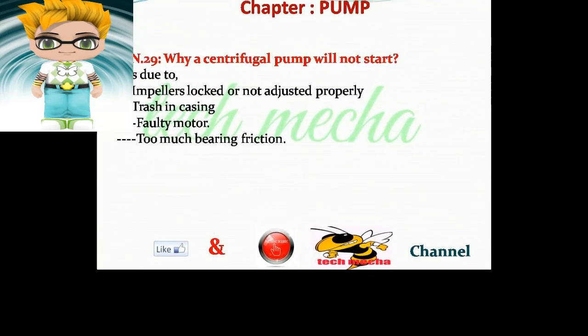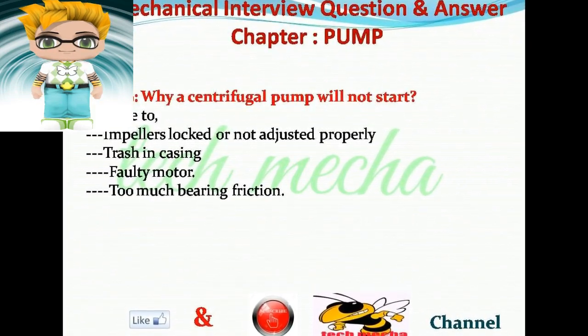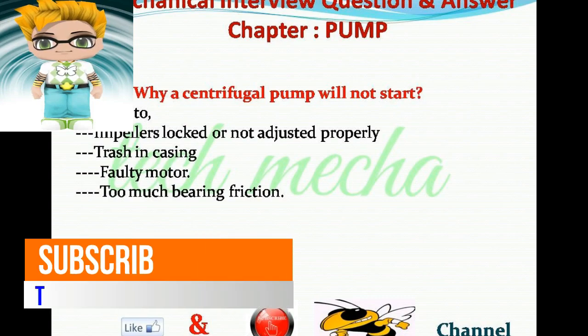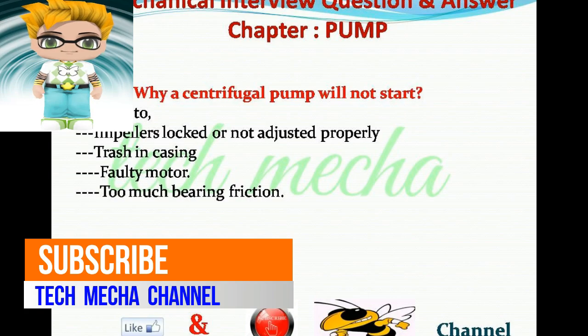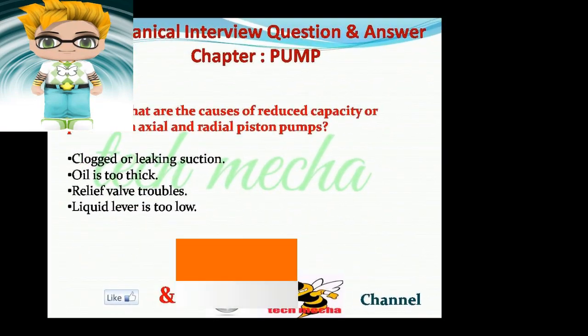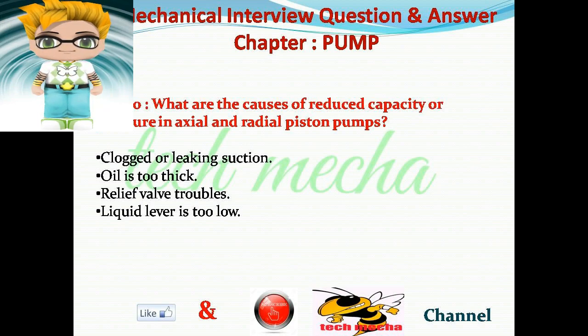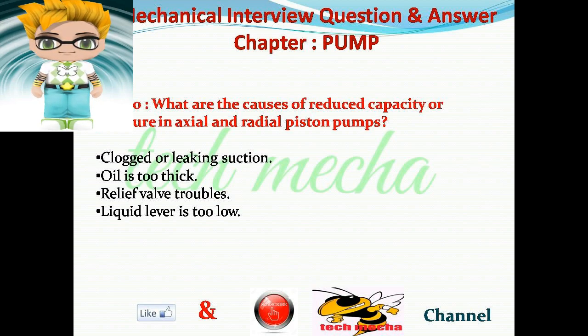Question number 29: Why will a centrifugal pump not start? Answer: It is due to impellers locked or not adjusted properly, trash in the casing, faulty motor, or too much bearing friction. Question number 30: What are the causes of reduced capacity or pressure in axial and radial piston pumps? Answer: The main causes of reduced capacity are clogged or leaking suction, oil too thick, relief valve troubles, and liquid level too low.